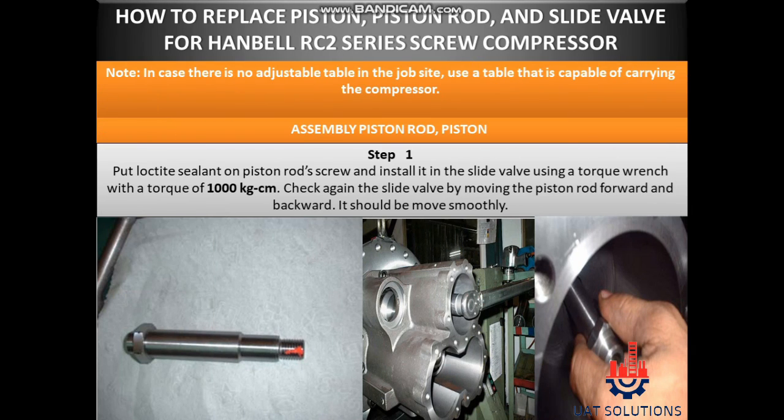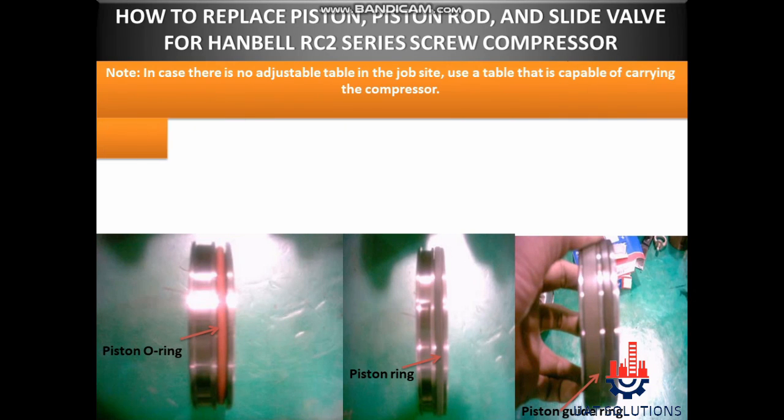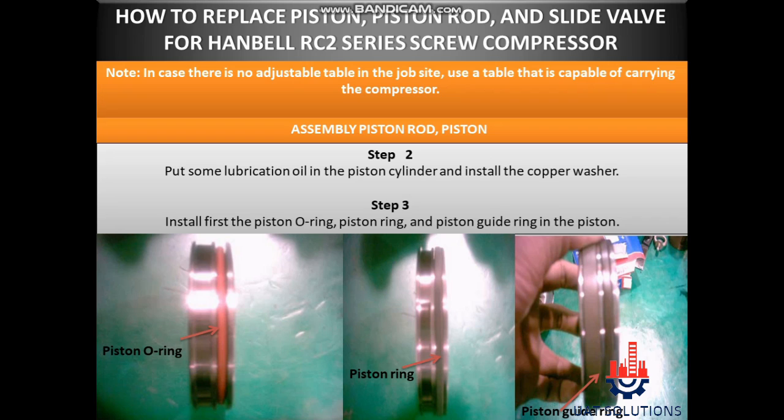Assembly piston rod. Step 1: Put Loctite sealant on the piston rod screw and install it in the slide valve using a torque wrench with a torque of 1000 kg·cm. Check again the slide valve by moving the piston rod forward and backward — it should move smoothly. Step 2: Put some lubrication oil in the piston cylinder and install the copper washer.